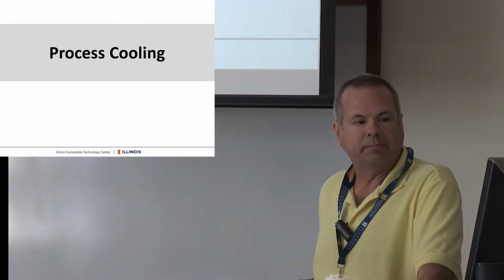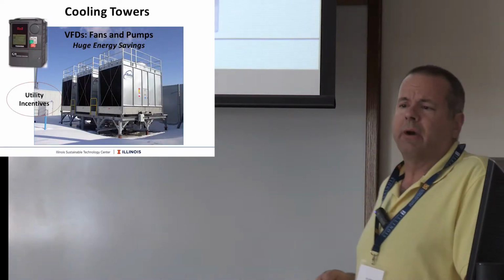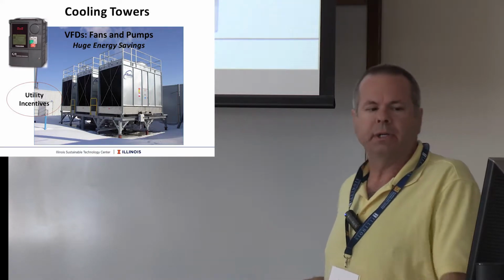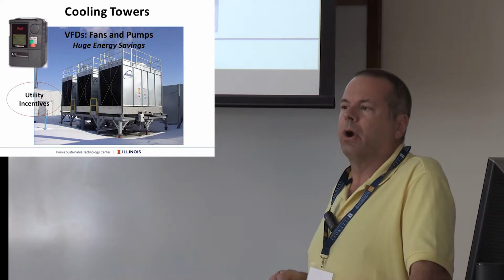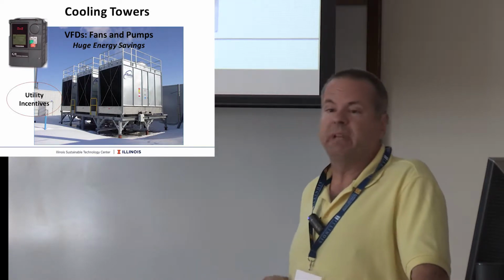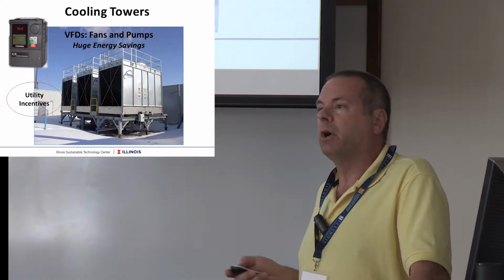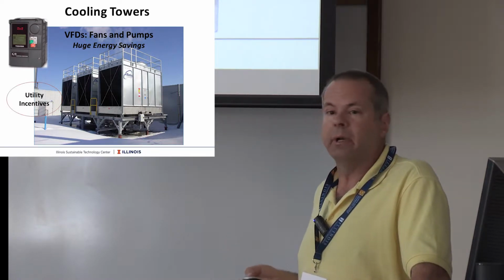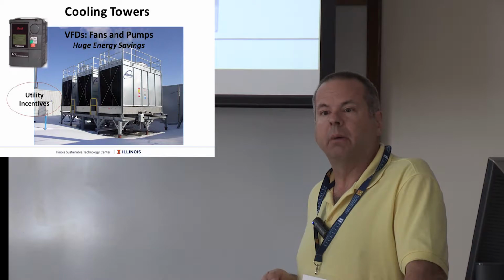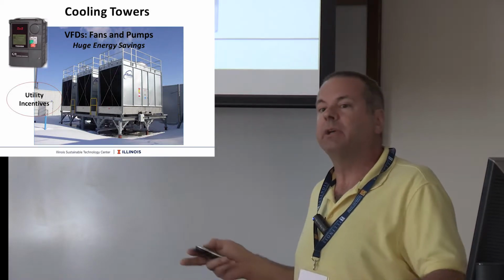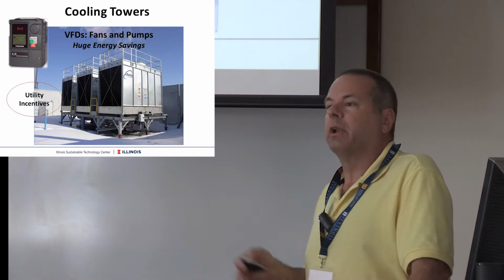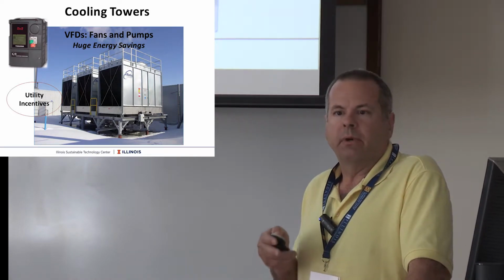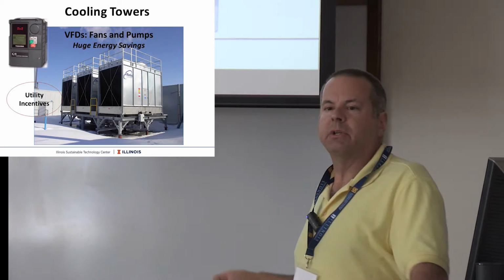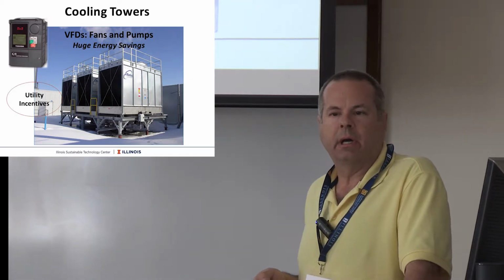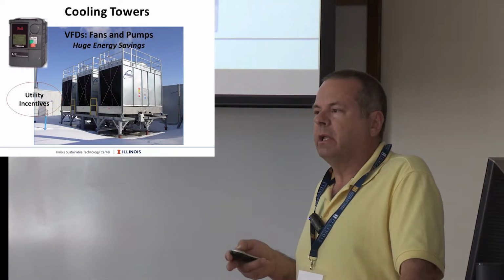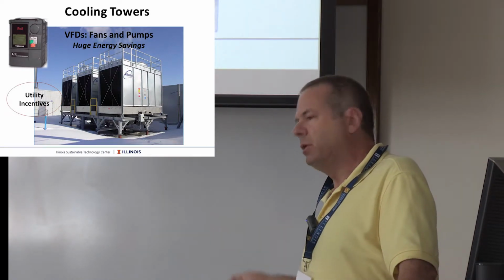Process cooling. If you have process cooling, cooling towers are energy hogs every day of the week. It's not unusual to see large two-speed fans on a cooling tower, multiple 25, 50, I've seen 200, I've seen 300 horsepower supply pumps, and sometimes they're combating each other, and they're being brought online, going to a common header. Usually they're running wide open in the summer because you can't get enough cooling capacity on the hot summer days here in Illinois, but in the fall, spring, and winter, they may be running one, then have to run two, then have to run three.